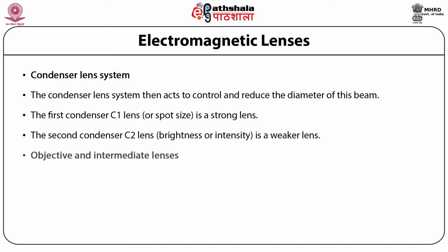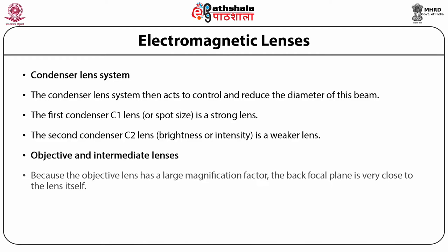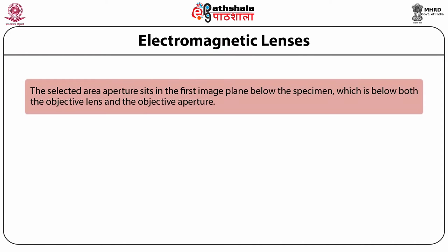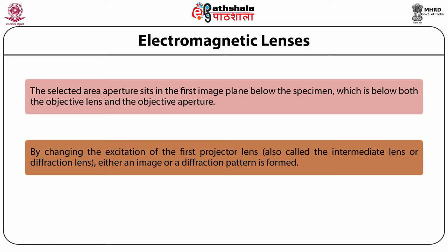The objective lens has a large magnification factor, with the back focal plane located very close to the lens itself. The objective aperture — the middle aperture on the column — is mounted in the back focal plane. Inside the first image plane beneath the sample, a selected area aperture is placed underneath both the objective lens and the objective aperture. By altering the first projector lens excitation, also known as the intermediate or diffraction lens, either an image or a diffraction pattern is produced.